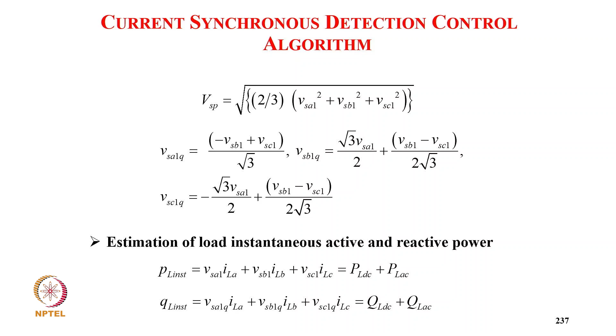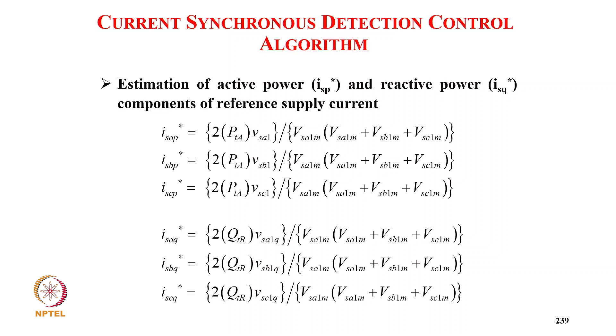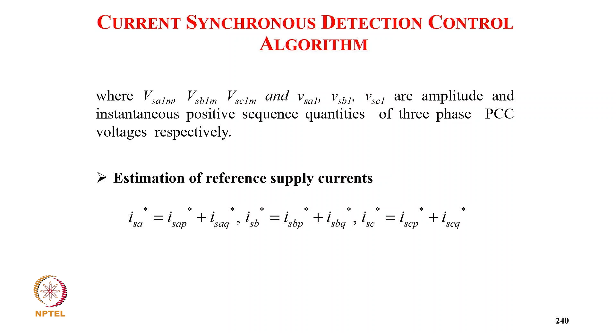Similarly for reactive power also, active and reactive power, which we filter, and we take a loss component for active power and voltage regulation for reactive power. And then from this active and reactive power we are able to calculate the active component of the reference supply current and then the quadrature component of the supply current reference. From this relation of calculating power and voltage, we are able to estimate both components. We get the supply current reference ISA star, and then we send it to the PI controller along with the sensed current. We get the pulse control.